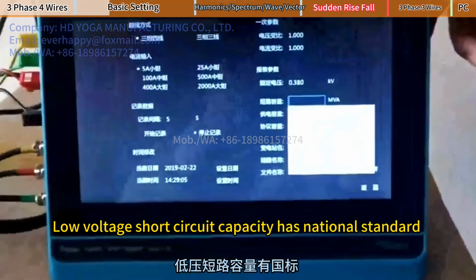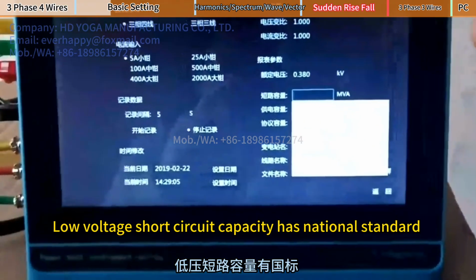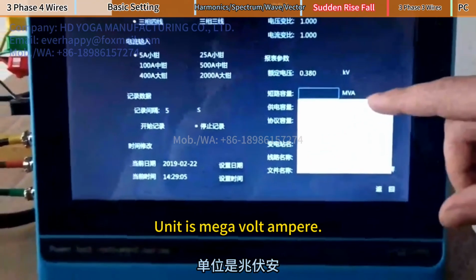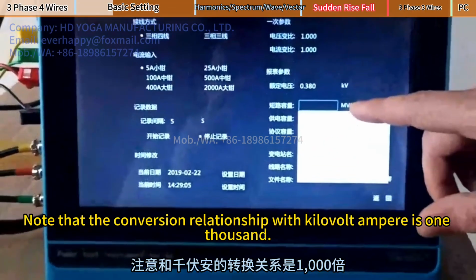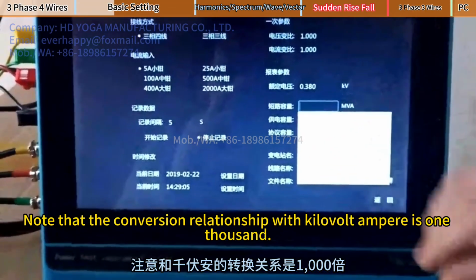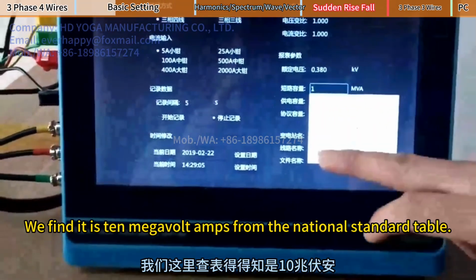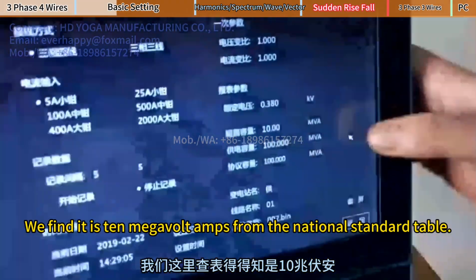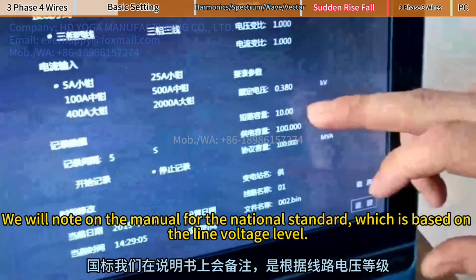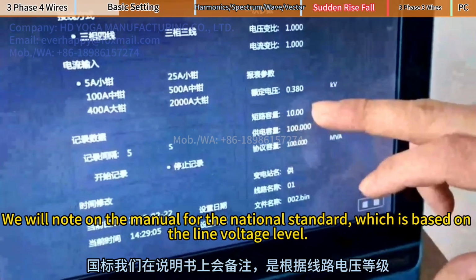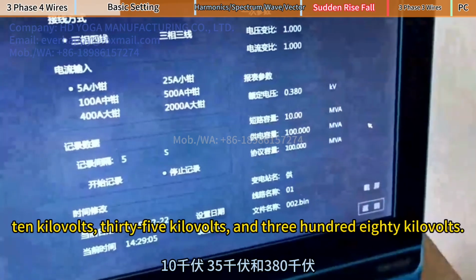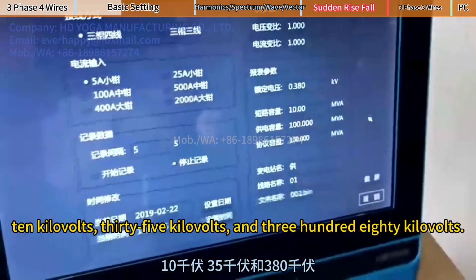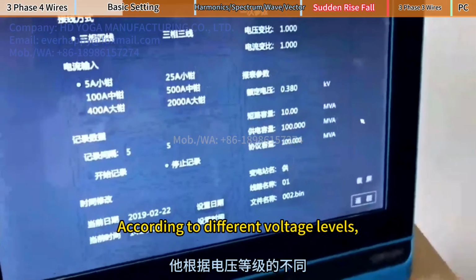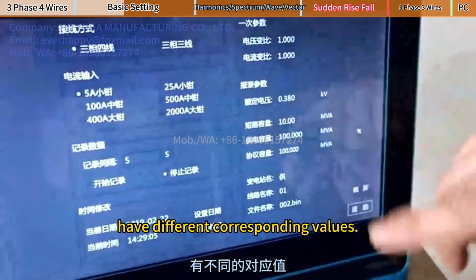Short circuit capacity is checked according to the different voltage levels of the national standard. Low voltage short circuit capacity has a national standard. Unit is megavolt ampere. Note that the conversion relationship with kilovolt ampere is 1000. We find it is 10 megavolt amps from the national standard table. We will note it in the manual for the national standard, which is based on the line voltage level: 10 kilovolts, 35 kilovolts, and 380 volts have different corresponding values.